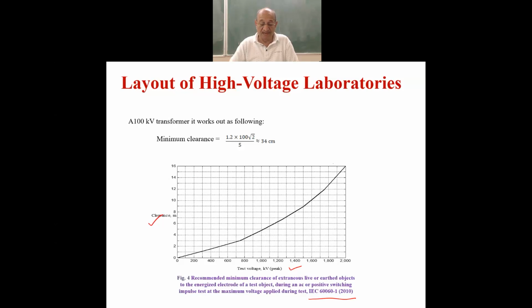The recommended minimum clearance of extraneous live or earth objects. I mean, clearance not only with the grounded objects, but with other energized objects also comes into the picture. There are two equipment, and suppose both of them are working at the same time. So what should be the clearance? The clearance is not only with the grounded objects but also live objects, to the energized electrode of a test object during an AC or positive switching impulse.